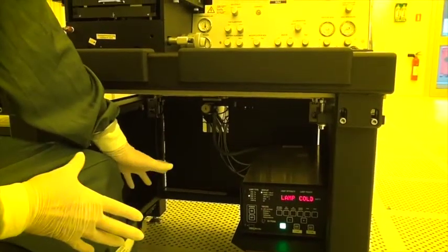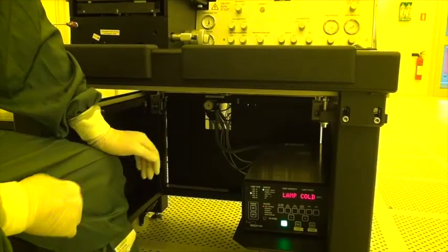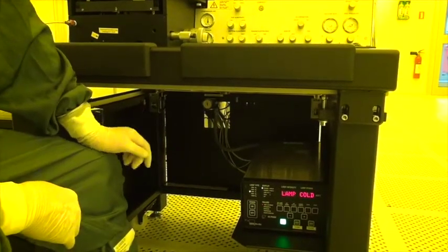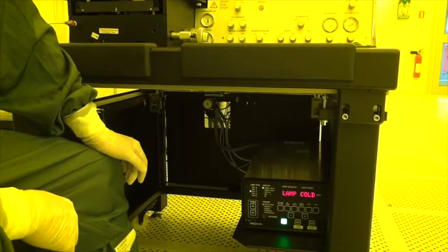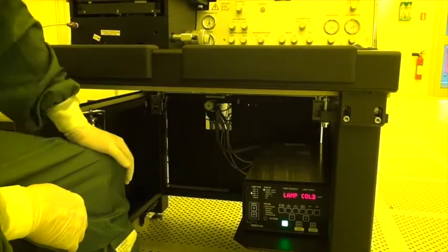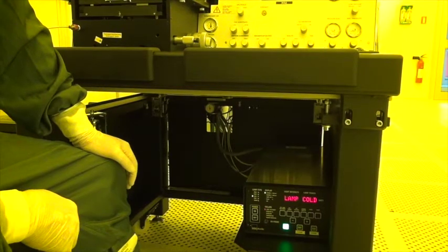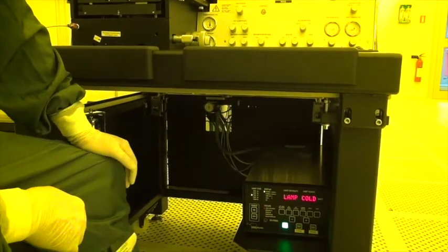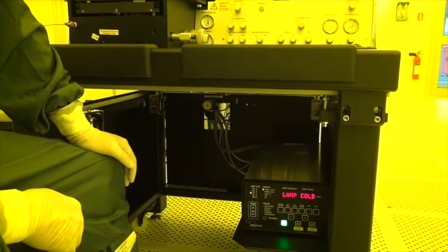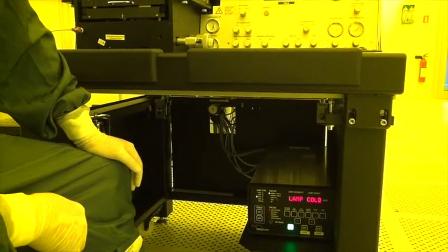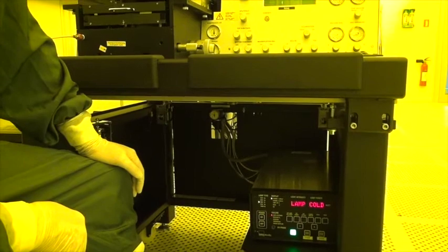The lamp is now ignited and has a warm-up sequence ramping up the power. And during this the power supply will indicate lamp cold. Once the lamp is ramped up it should be allowed to warm up completely and stabilize for about 15 minutes.